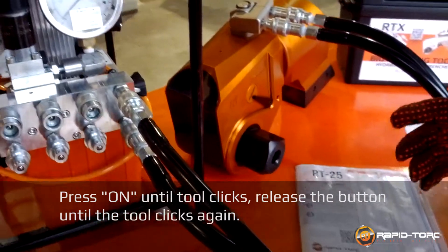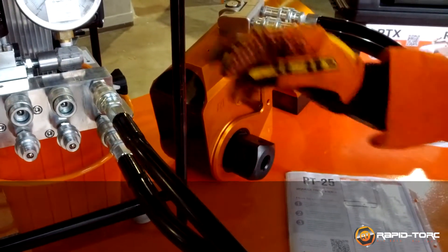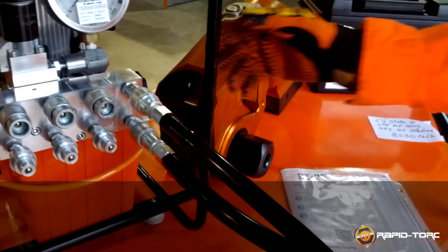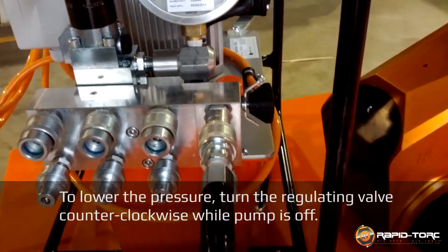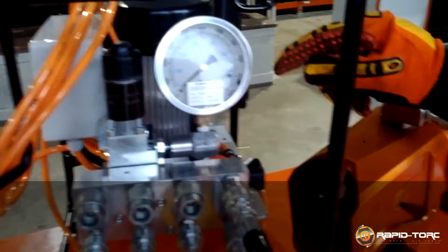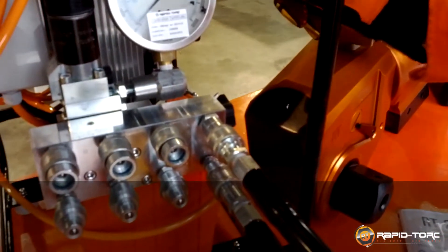You will hear click, click, click, click as the piston advances. When you reach 3100 psi and need to set up for a smaller pressure to untighten, go again in pressure — but never make the regulation go downwards; always go upwards for the regulation. Then push.